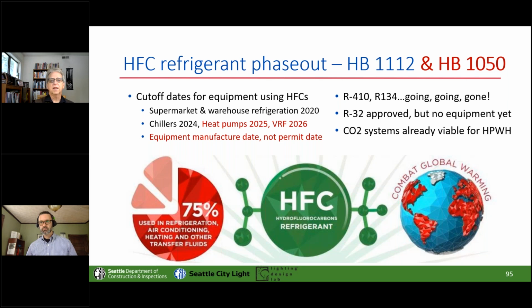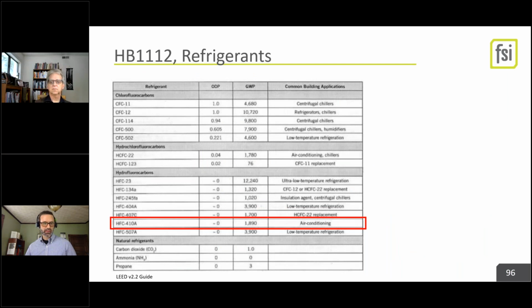And for equipment that uses that, this is when the equipment is manufactured and not when the building permit is happening. And so the equipment is usually manufactured a few months maybe before the actual install. And so I think that things that are going in for permit for larger buildings pretty much now are going to be governed by this new rule. So say goodbye to R410, R134, those are going away real soon. So we've got 10 minutes left, right? I think I'm going to move real quick through refrigerant slides.